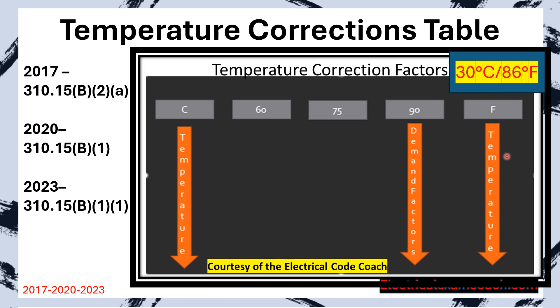Once we know we're in the right table, let's break it down. On the left-hand side we find the column in Celsius — if your ambient temperature is in degrees Celsius, start there. Across the top you'll see 60, 75, and 90 degrees C columns, which correspond with the 60, 75, and 90 degrees C columns of our starting ampacity table. On the right-hand side you'll find degrees Fahrenheit, used when your ambient temperature is listed in Fahrenheit.